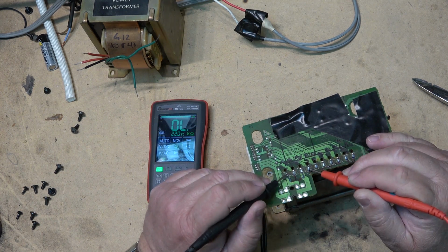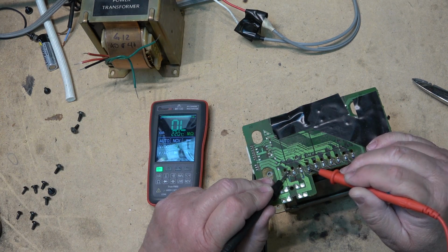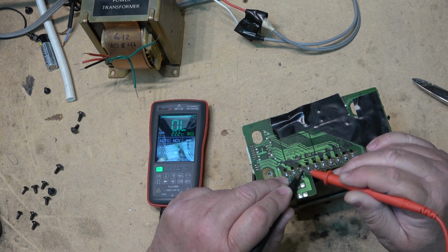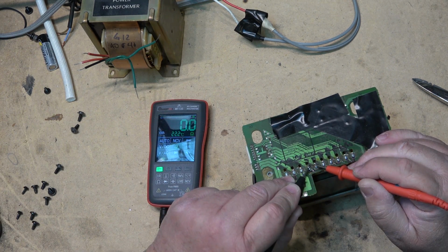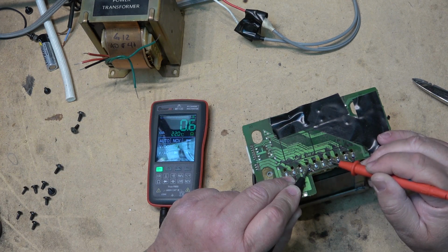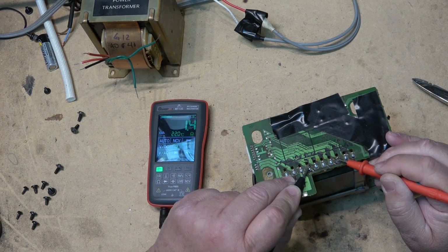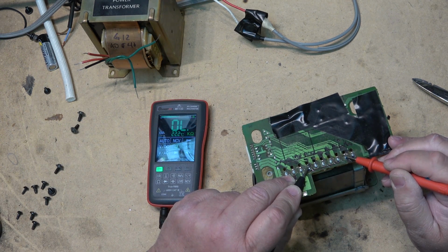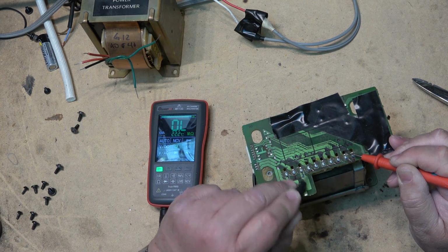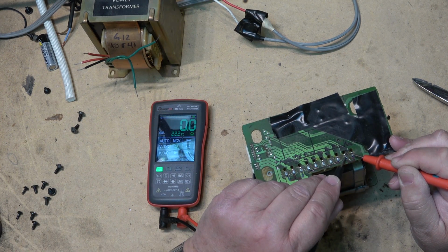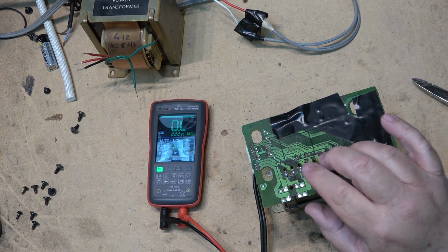That's one winding. It's open between these ones, so this is a standalone winding. These ones here, we have continuity between all 4 of these windings, and it's open here as well. And then this one here is its own standalone winding. So we've got 3 separate windings.